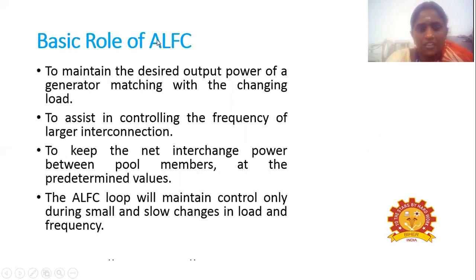So the basic role of ALFC, automatic load frequency control. The first role is to maintain the desired power output of the generator, matching with the change in load, and then to assist in controlling the frequency of large interconnection, and to keep the net interchange power between the pool members at the predetermined values. So these are some of the basic roles of the ALFC loop. The ALFC loop maintains control only during small and slow changes in load and frequency.